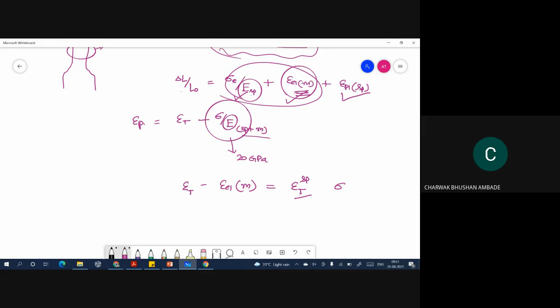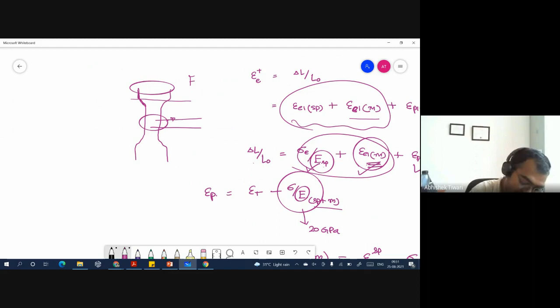Okay, no issues. So we use an instrument which is called an extensometer, and that has clips on the sample, and it has a strain gauge. So it's a part of instrumentation. You have a Wheatstone bridge kind of thing inside, and as the sample diameter decreases as you elongate it, the clips which you have fixed on the sample will also get compressed like this, right?